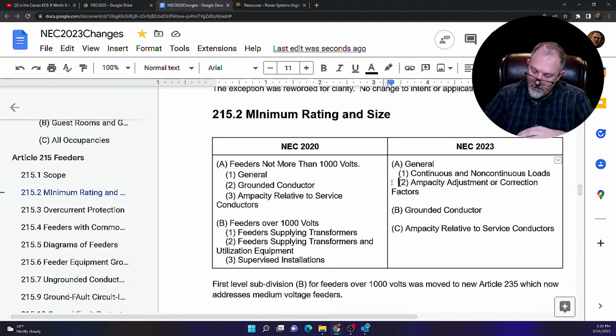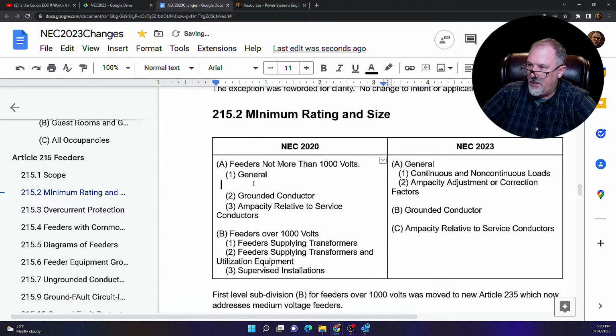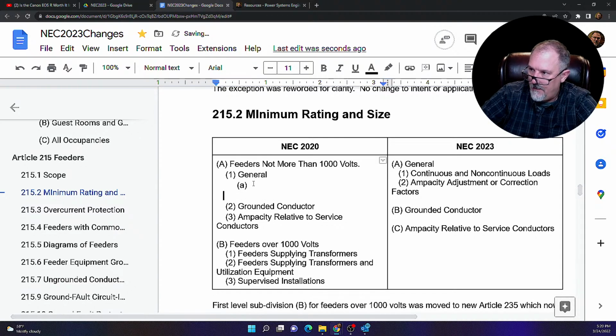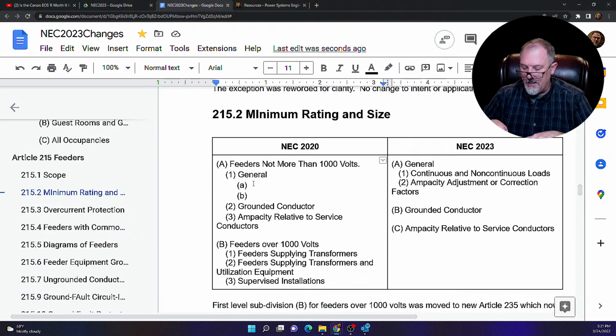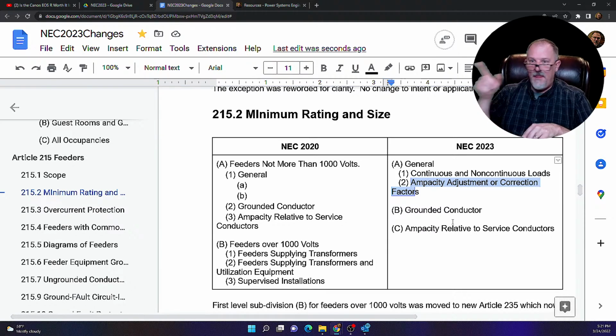General. Okay. So remember, in general, you had an A and you had a B. Right, so A was where a feeder supplies continuous loads or any combination of continuous and non-continuous loads. Look what they did. We created a second level subdivision called continuous and non-continuous loads, and we put that text there. And then you had B, the minimum feeder or conductor size shall have an ampacity not less than the maximum load to be served after the application of adjustment or correction factors in accordance with 310.14. And what did we do? We created a second level subdivision called ampacity adjustment or correction factors, and we put the text that was in 215.2A1B there, or there.